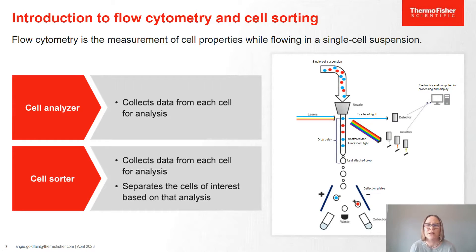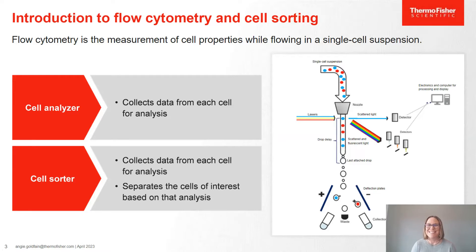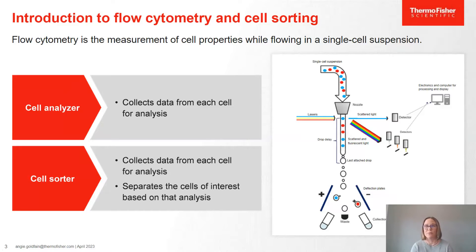Flow cytometry is the measurement of cell properties while flowing in a single cell suspension, and that single cell suspension is really key. A cell analyzer collects data from each cell for analysis only, whereas a cell sorter does that and takes it to the next level, letting you separate the cells of interest based on that analysis. This starts with a single cell suspension, which is focused into a stream and then interrogated by one or more laser beams. The single cell suspension is in a carrier fluid called the sheath, which presents the cell to the interrogation point where the lasers hit the cells. From there, we collect light coming from each cell, separate by wavelength, and digitize for processing and display to the user.